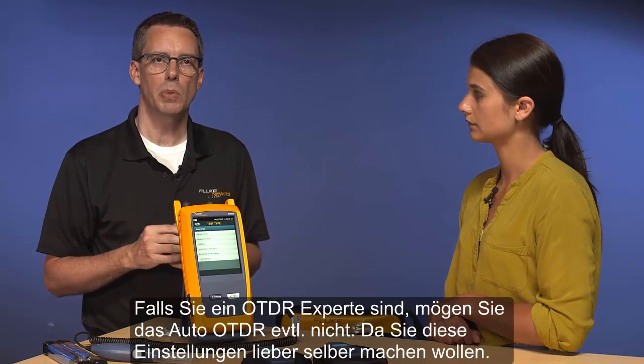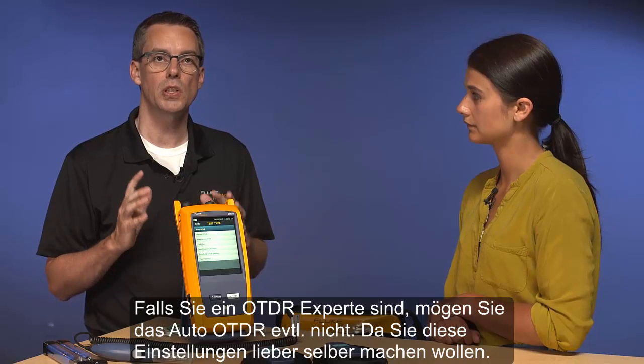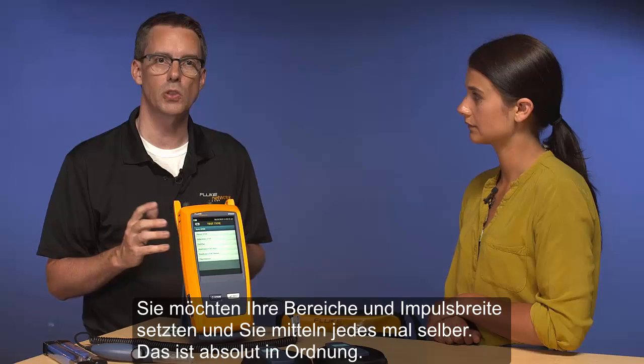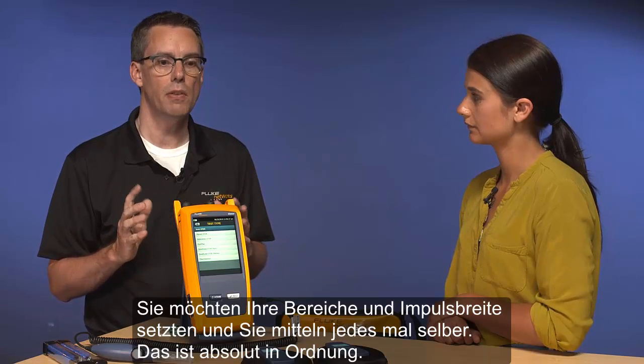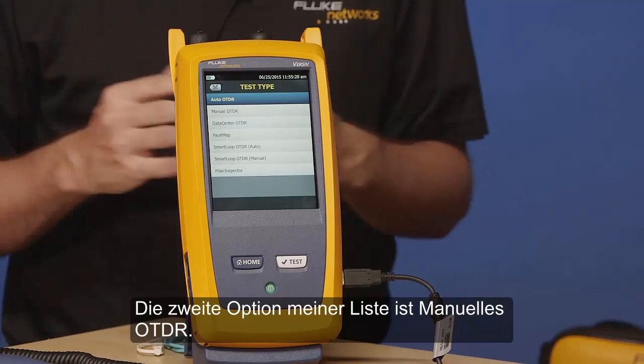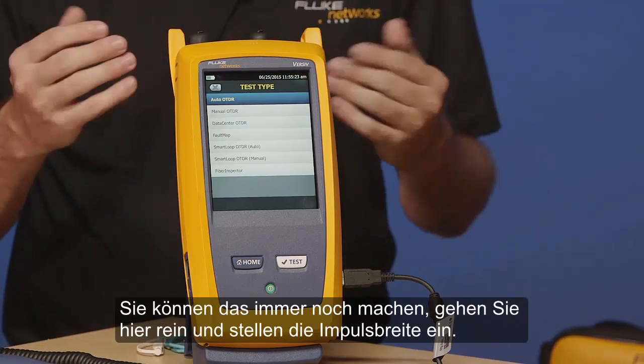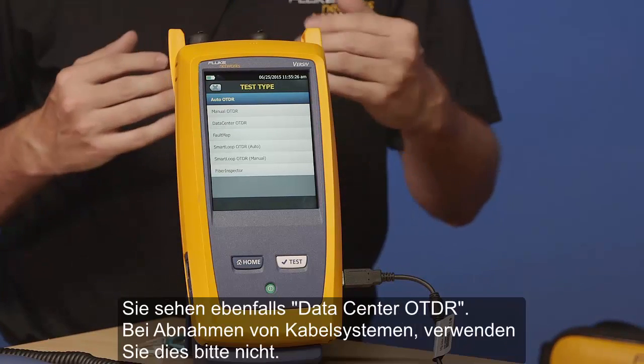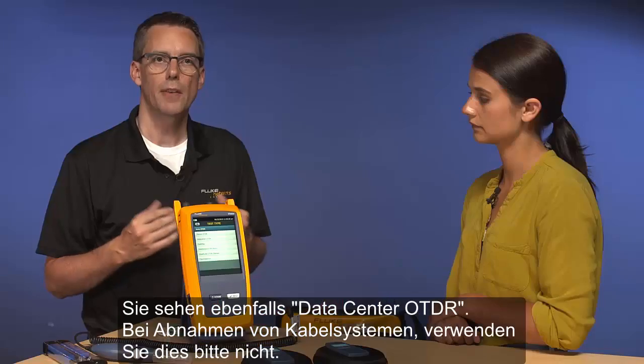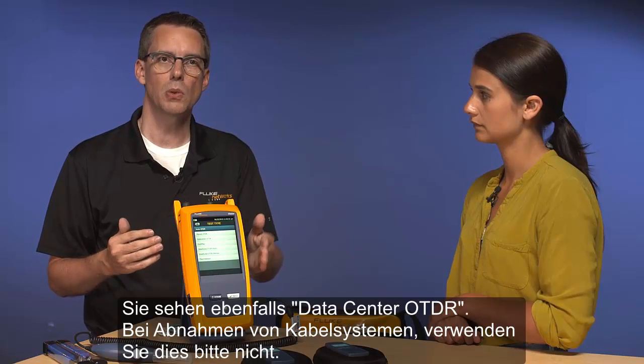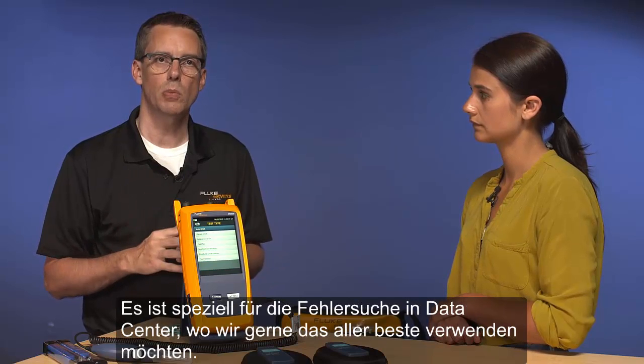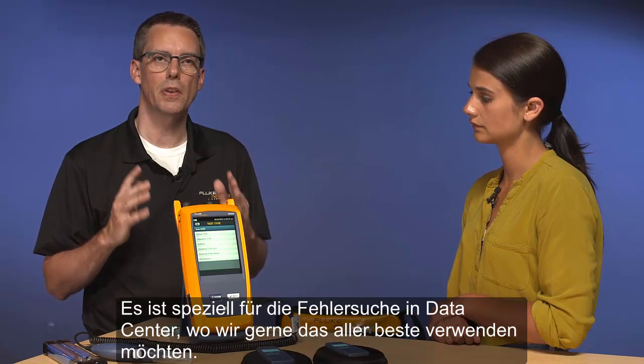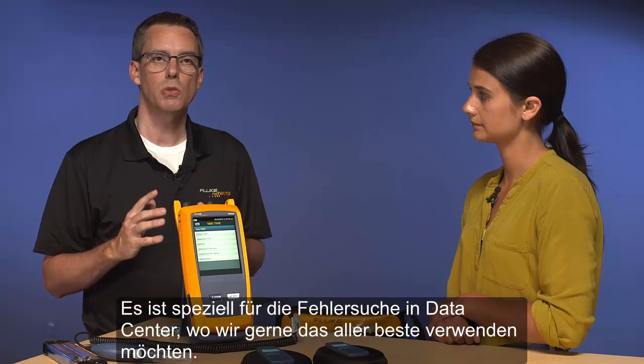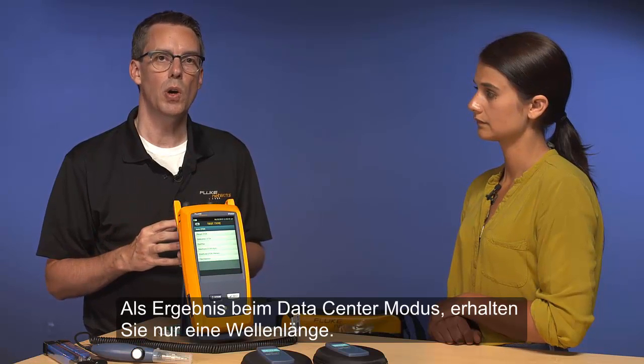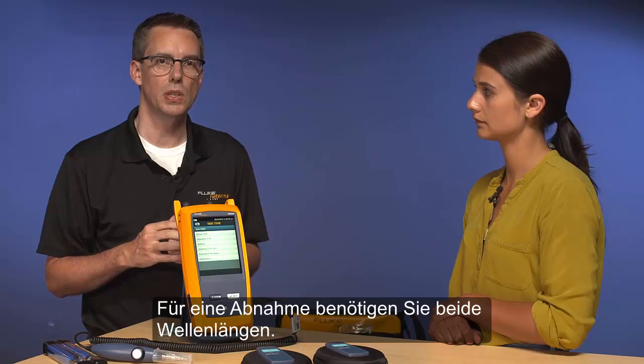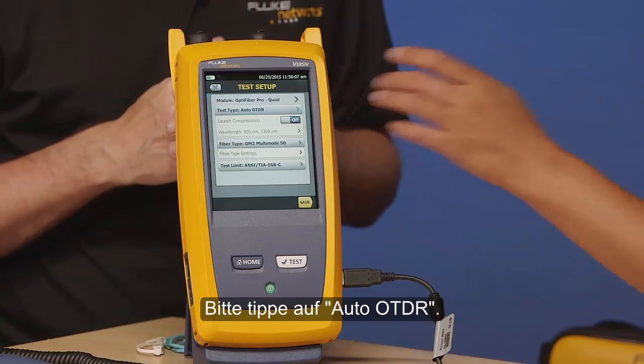Now, if you're an OTDR person, you may not like Auto OTDR and you want to set this up yourself, you want to set your ranges and your pulse widths and your averaging down yourself. That's totally fine. Second option on the list here is manual OTDR. So you can still do that, go in there and set up all your pulse widths in there. You'll also see data center OTDR. If you're doing certification of cabling systems, please don't use this one. This one is specifically for troubleshooting in data centers where we want to try and get the very best dead zone possible. As a result, if you use data center mode, you only get one wavelength. You need both wavelengths if you're doing certification. So go ahead and tap Auto OTDR.